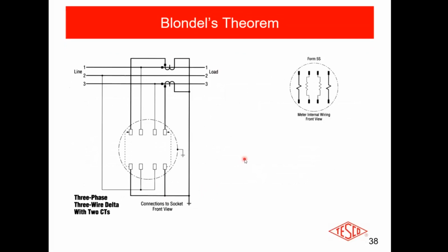So let's talk about 5S. If you manufacture test equipment, you hate 5S meters because they're different from every other form. If you're a meter tech out in the field or a meter engineer setting up field installations, you'd love a 5S because you can get a 5S to meter virtually anything. But you can set them up in a wide variety of ways. So here we're going to meter a 3-phase, 3-wire delta system with 2 CTs. Okay? Fairly basic fundamental setup.